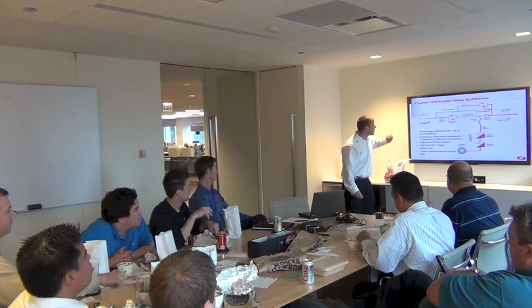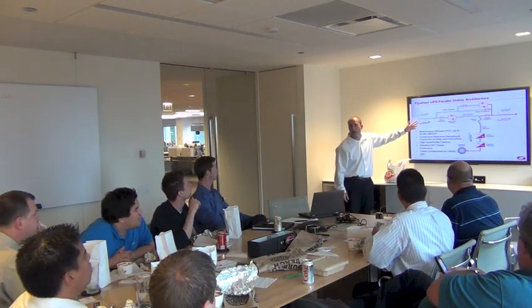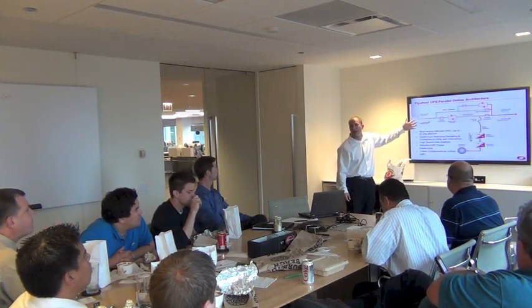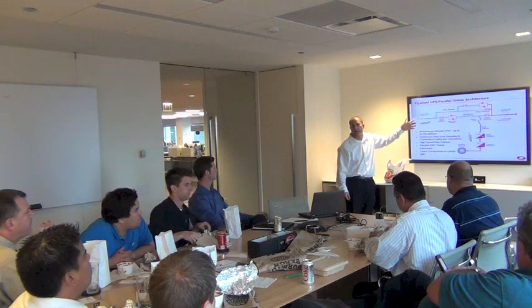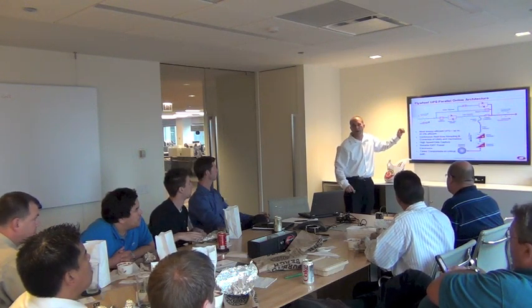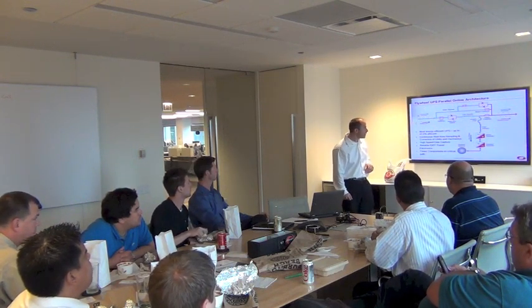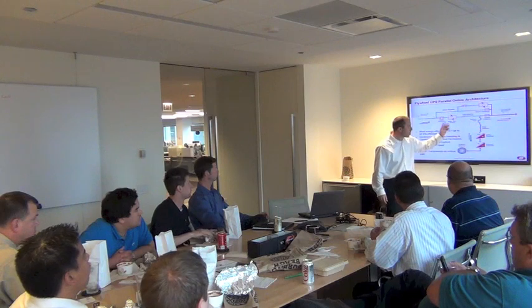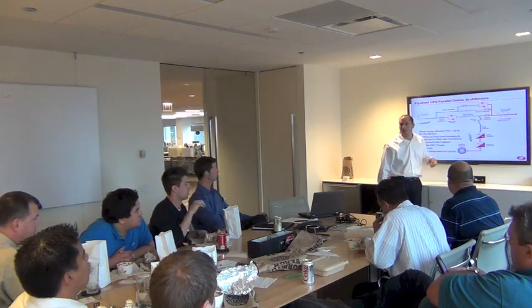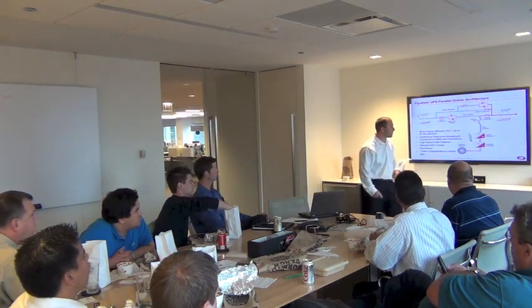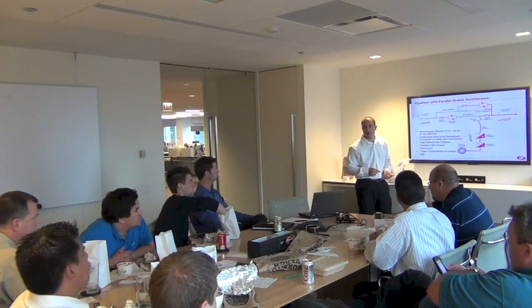We also have a very, very fast sample rate. So we sample on each phase 333 times every cycle, so once every 50 microseconds. So very, very fast sample rate. Basically, this guy right here, in normal operating mode, he's acting as a variable frequency drive, and he's driving this flywheel always at 7,700 RPMs.